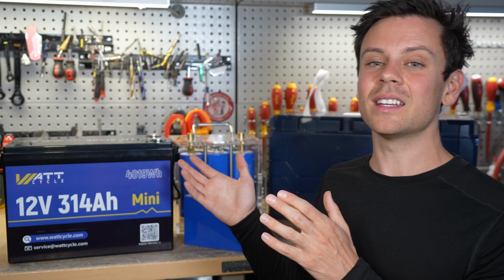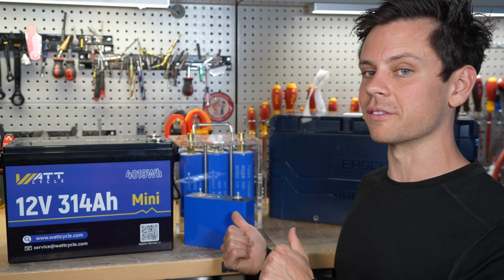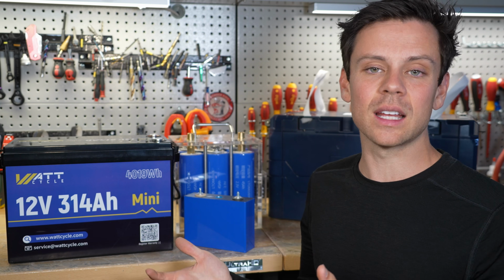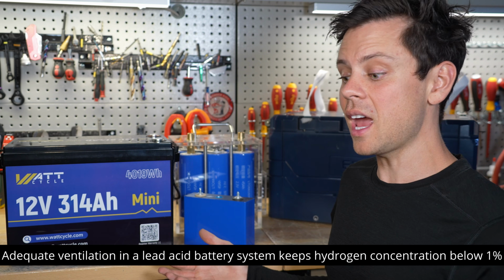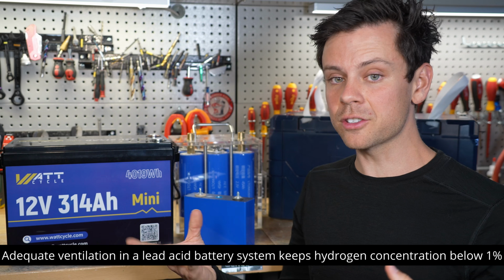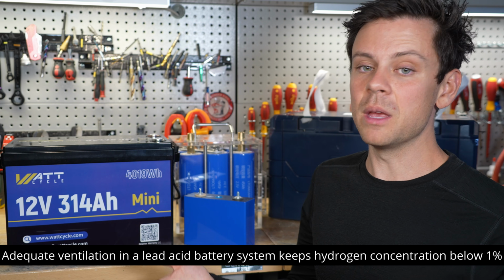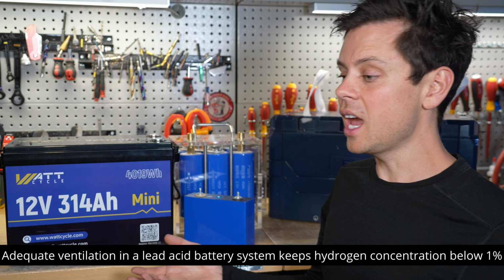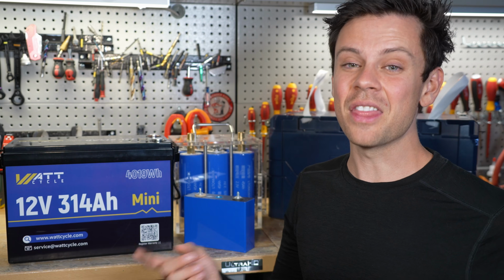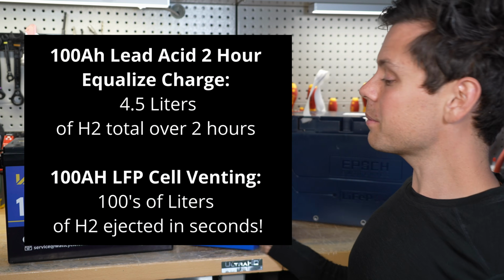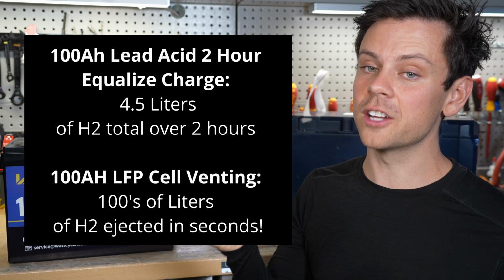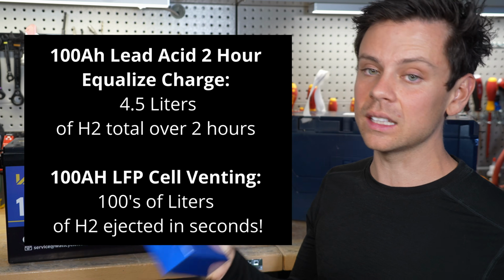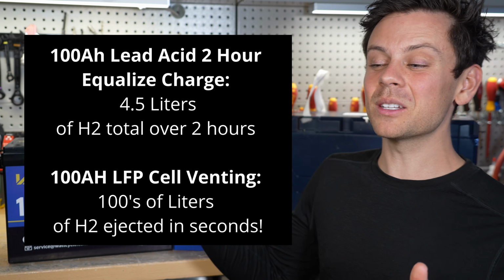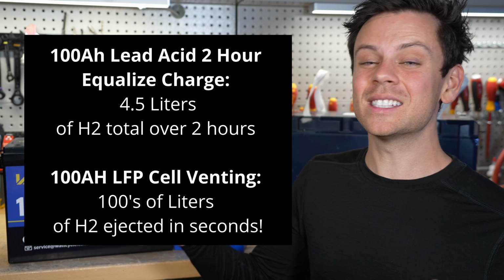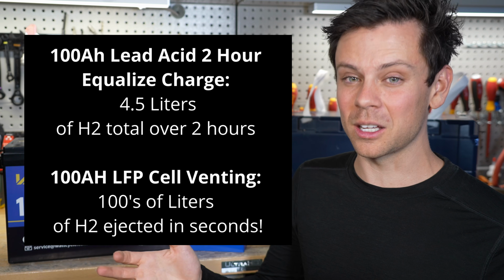Keep in mind that designing a ventilation system for lithium iron phosphate is not the same as for lead acid batteries. A lot of people think, hey, lead acid bubbles off hydrogen on the equalized charge, so maybe I could just use a system like that and hydrogen won't accumulate. That is not true. Lithium iron phosphate gives off a lot more hydrogen much faster than any lead acid battery bank.